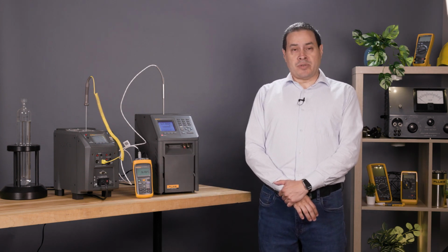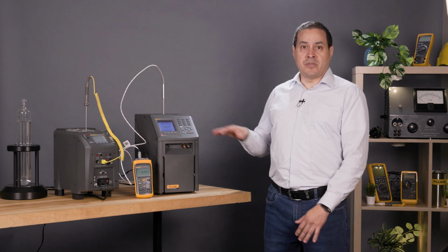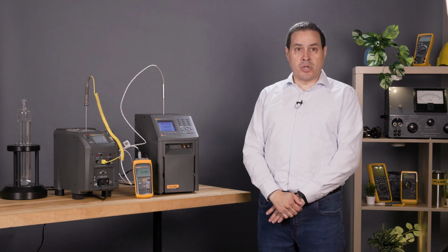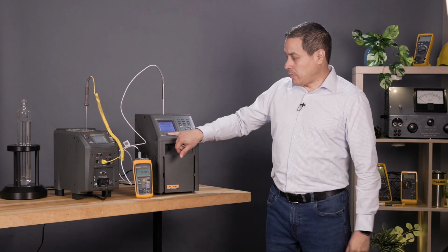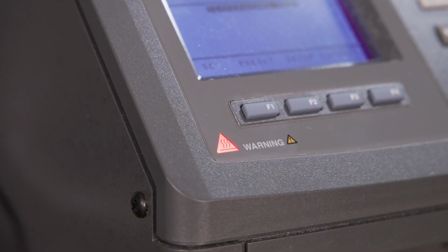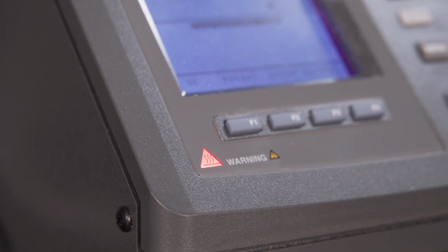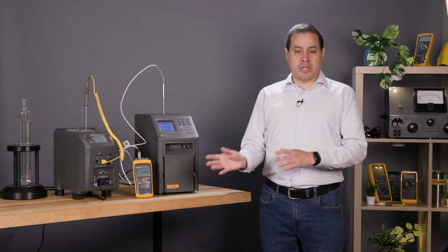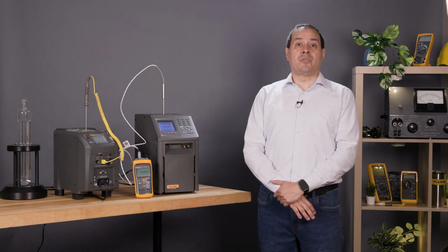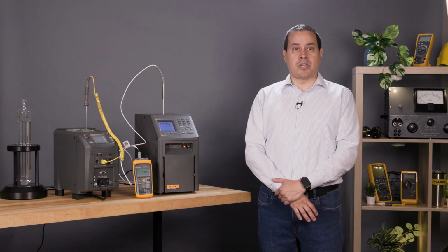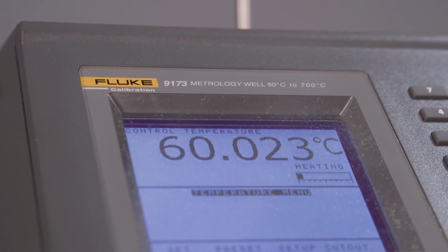And then you need to wait until it stabilizes. It will emit a beep, so you will know it's safe to take the point. Pay attention when the warning sign is on, because you may get burned. Be careful. Once it stabilizes, we can take the measurement for the dry well. On the unit under test, we can go to the software, or if you don't have any software, a piece of paper, to get the measurement now stabilized. So we can move on to the next steps.